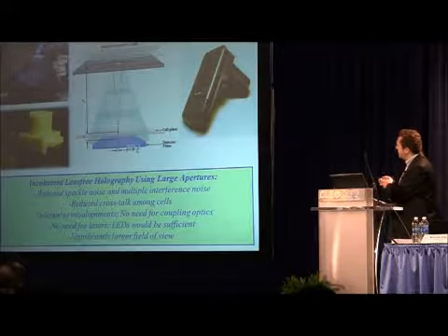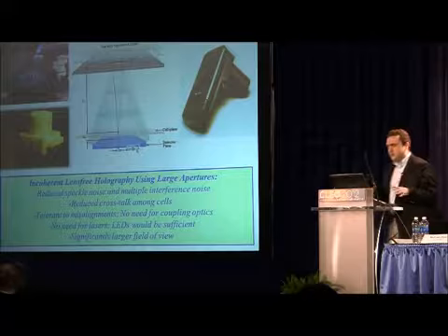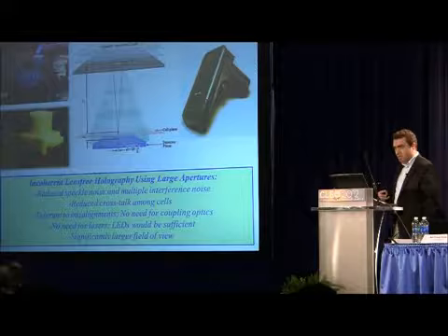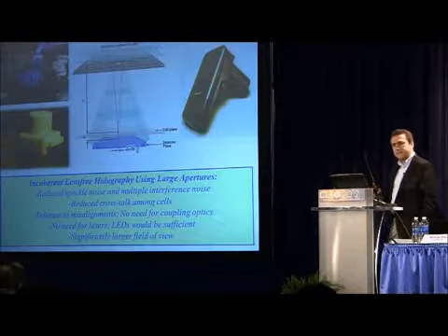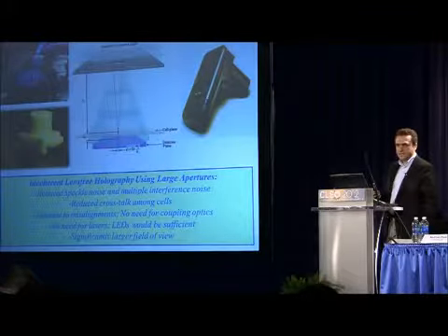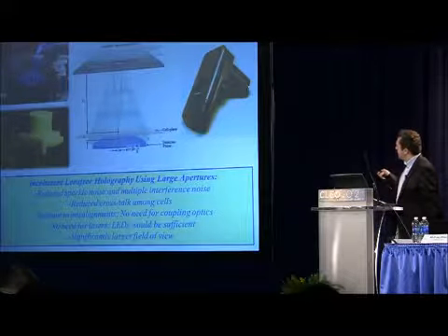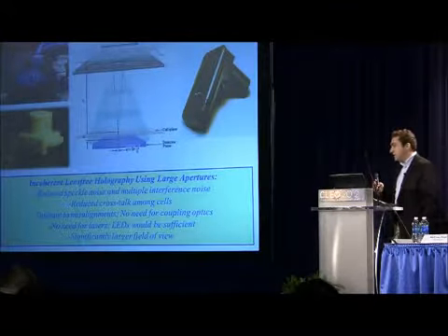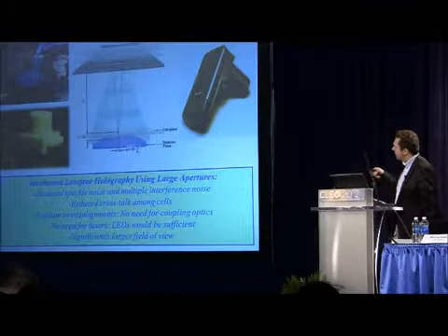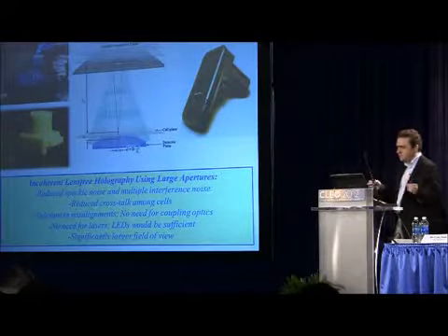So whether it's running on a cell phone or a standalone unit or a benchtop system, as shown here, these microscopes, these microanalysis tools, are actually working based on partially coherent illumination. So it's holographic in the sense that we are recording fringes that convert the phase information of the specimen into intensity oscillations. However, the source is not a laser, it's actually a light emitting diode. It could be sunlight as well. And what we do is we play with the geometry of this microscope so that we have partial coherence that's sufficient to record holograms of individual cells.